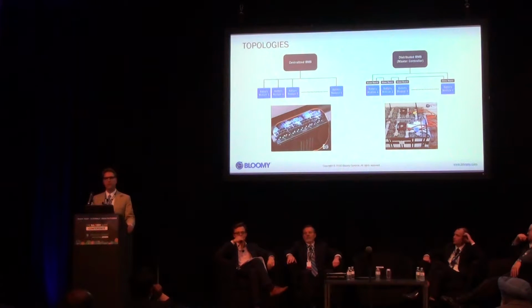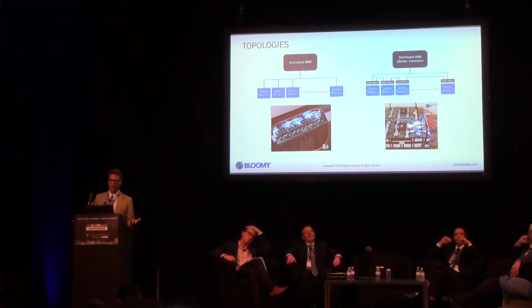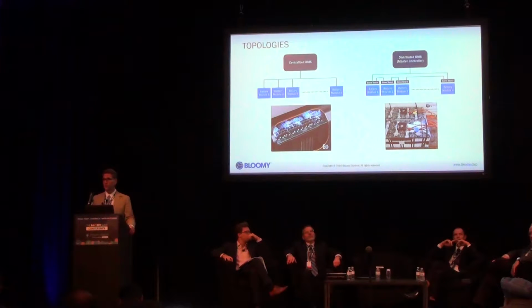The benefits of the distributed BMS, which is pretty much the dominant design for a lot of applications, including hybrid and electric vehicles as well as energy storage systems: it's more noise immune, and the slave boards require less isolation because they're only exposed to smaller modules of cells and not the entire pack. The master controller is responsible for things like monitoring all of those modules, monitoring the pack overall voltage and current, and opening the main contactor if there's any kind of a problem.